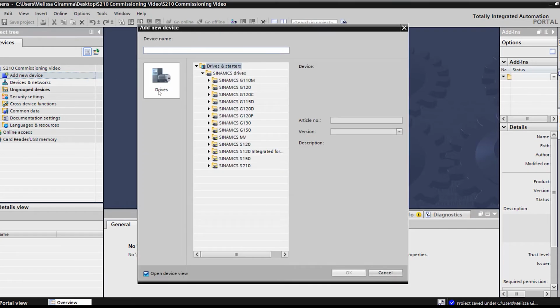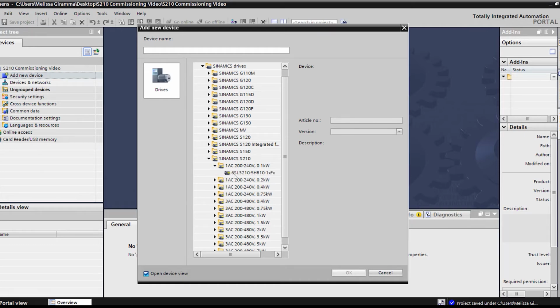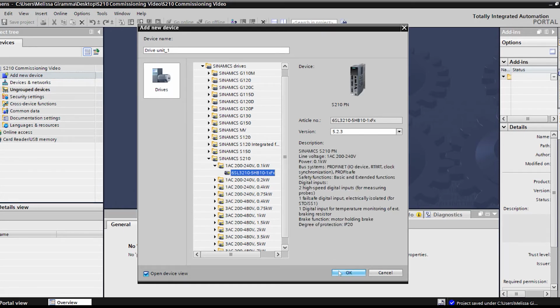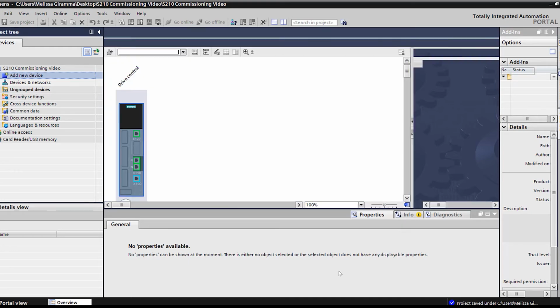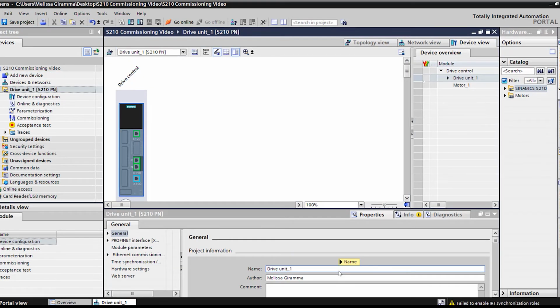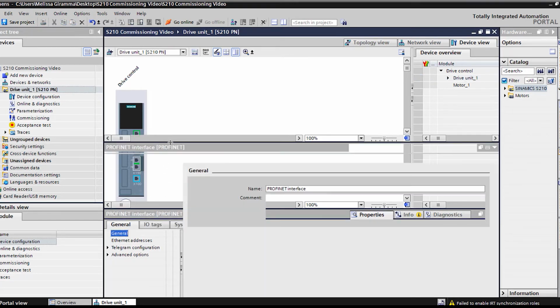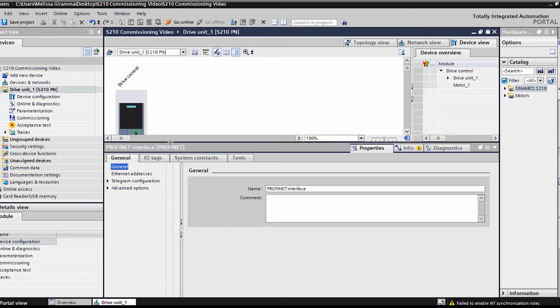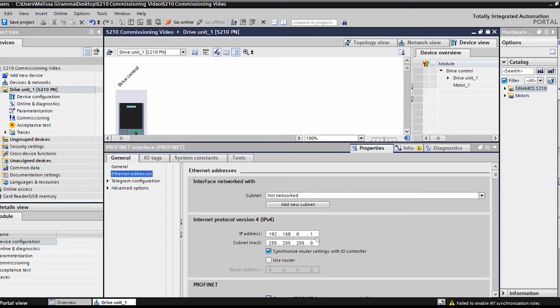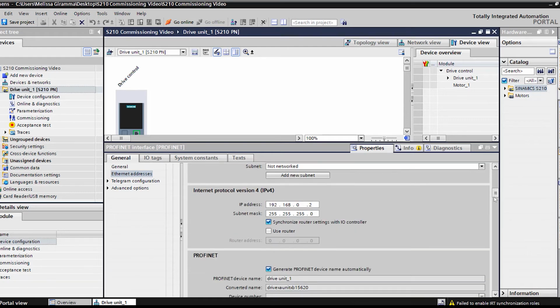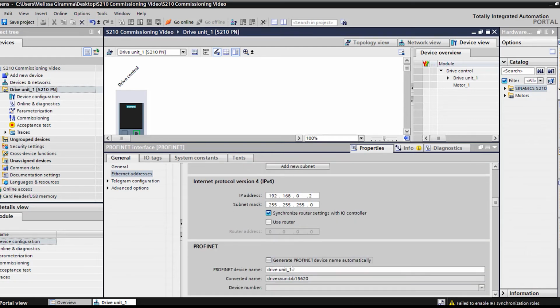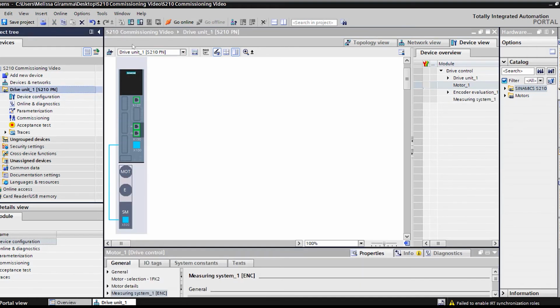you are using. The first step is to set the Profinet name and IP address. To do this, I like to double-click on the Profinet port on the S210 image and then expand the bottom portion here. Select Ethernet addresses and enter the IP address that you would like to use. If you scroll down, you'll see the section to update the Profinet name. Right now, we are offline, so we need to select Download to Device to transfer these settings to the S210.